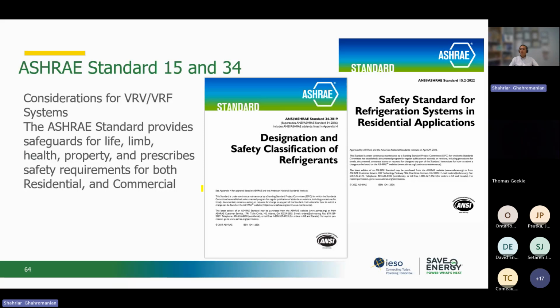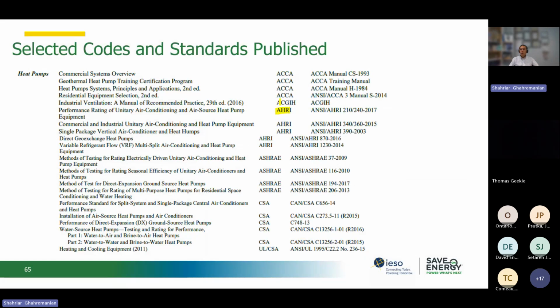But there are many other standards from AHRI or from CSA actually. So it's better that we review those standards, either for ground source heat pumps or for air source heat pumps. ASHRAE 90.1 also has some numbers about the efficiency of the systems. Again, we need to check those ones and then meet those minimum requirements.